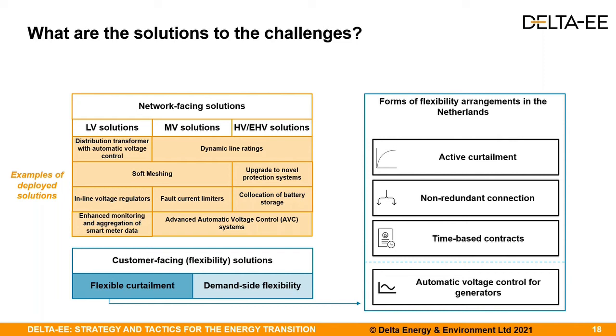And then the last one, automatic voltage control for generators. It's basically used when there are over-voltage problems in the grid. We ask customers to install automatic voltage control, where the reactive power consumption or production can influence the voltage level of the grid. Some parties are allowed onto the grid if they agree to use this solution, and of course, the power plant will automatically curtail if the voltage level rises too high.